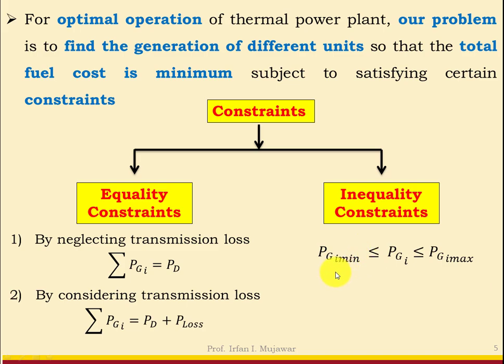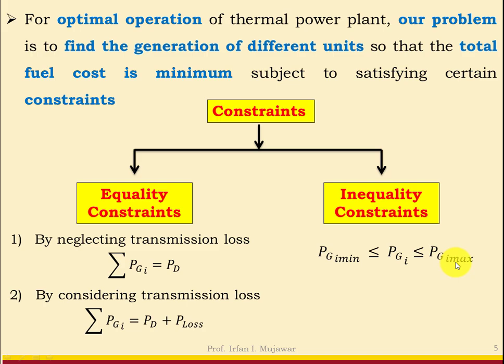The inequality constraint states: PGi_min ≤ PGi ≤ PGi_max, where i is the ith unit. Generation of the ith unit should always be less than or equal to its maximum generation and greater than or equal to PGi_min. The minimum condition is important because if generation is less than that value, thermal power plant operation is not economical or feasible. PGi cannot exceed PGi_max or there will be overloading and overheating problems.